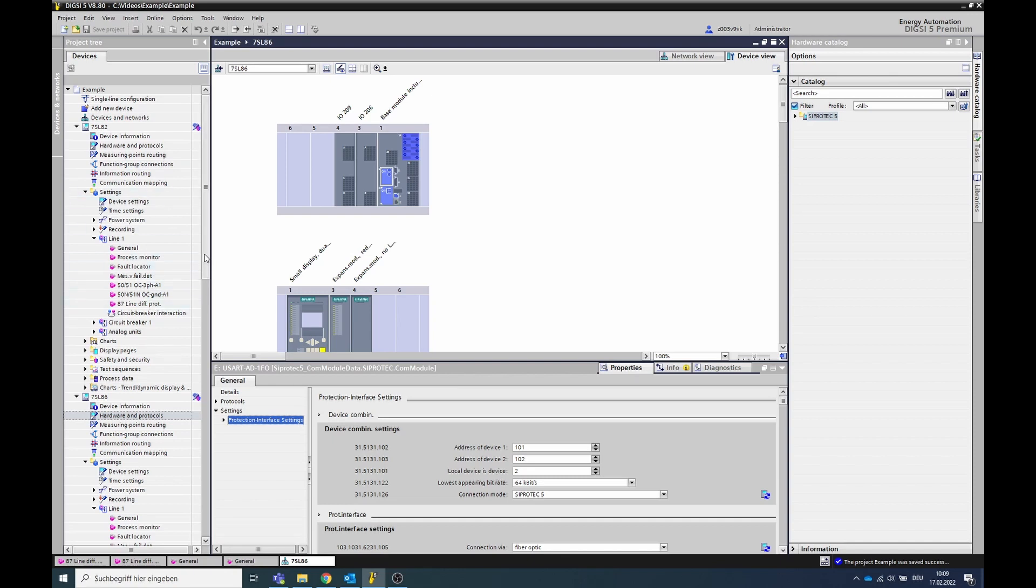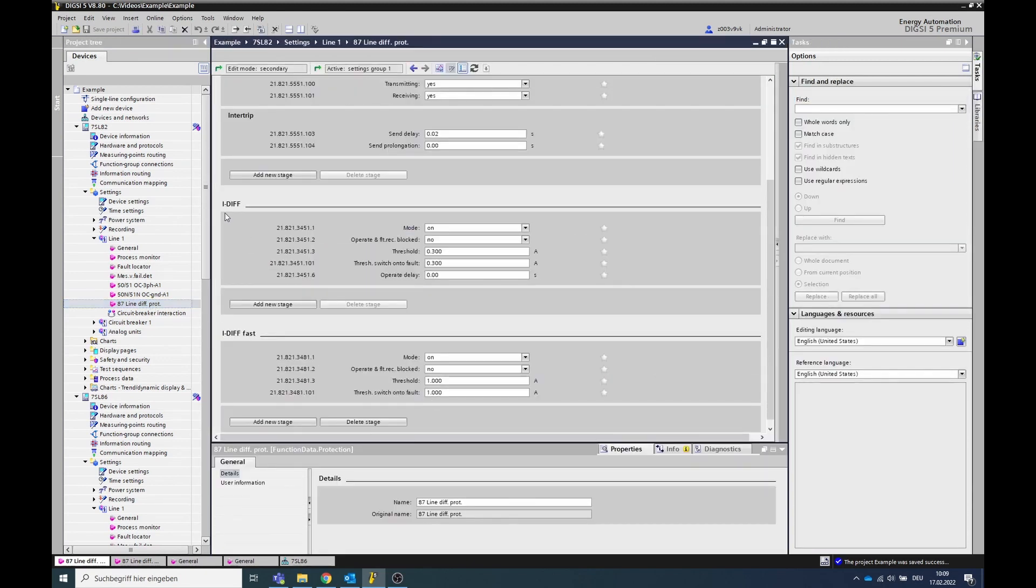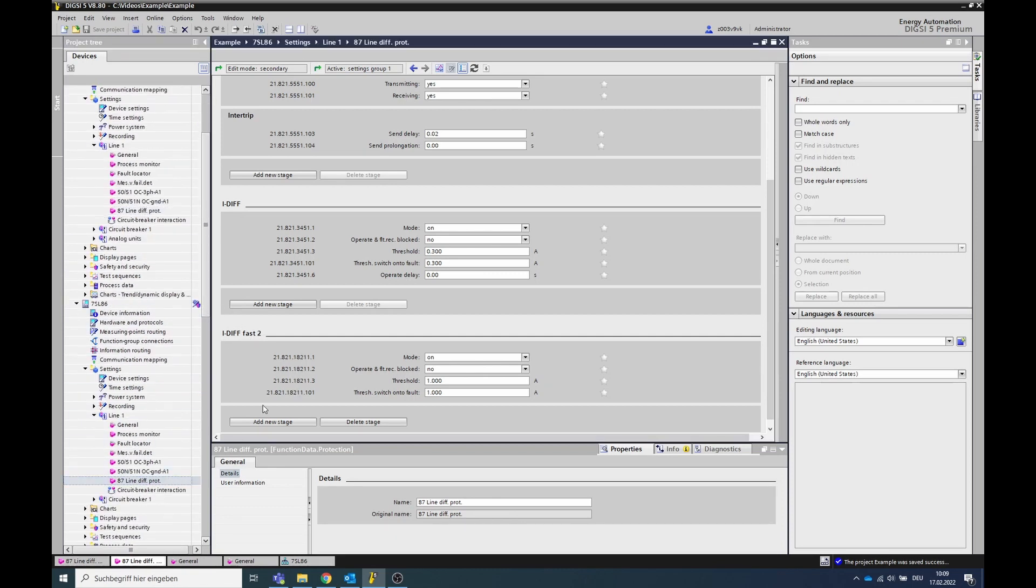Go to the line function group and open the line diff protection function. Check which stages are present in the function. Note that the same stage type must be instantiated in all devices of the device network. The devices of the device network work either with the stage iDiffFast2 or with the stage iDiffFast.